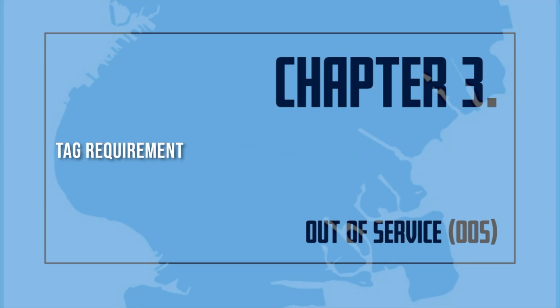Tag requirement. A tag shall be used to indicate that a system or portion is out of service. Fire Code 901.7.2. A master fire suppression piping contractor Class A or B, or a master plumber, as restricted, shall be required to post tags at the main control valve and at any closed sectional valve serving areas affected. The tag shall indicate the area affected, a brief description of the condition, the occupancy classification, C of F number, and the estimated time until the system becomes operational.